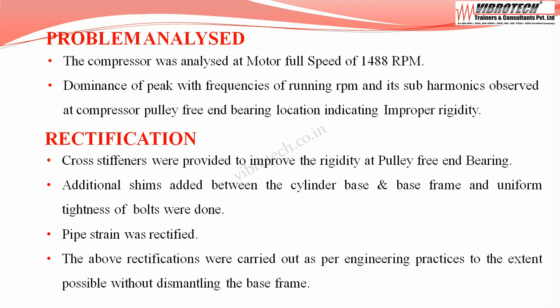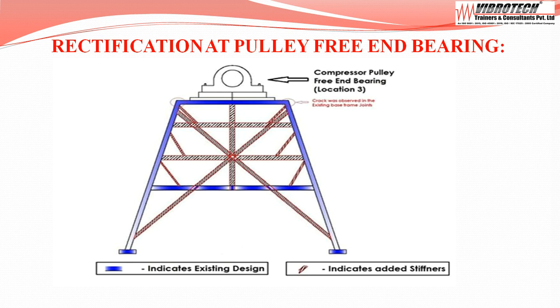To rectify the problem, the following activities were carried out: cross stiffeners were provided to improve the rigidity at the pulley free end bearing. Additional shims were added between the cylinder base and base frame, and uniform tightening of bolts was done. Pipe strain was rectified. These rectifications were carried out as per engineering practices, to the extent possible without dismantling the base frame. The picture shows the existing design and additional stiffeners provided at the pulley free end bearing.